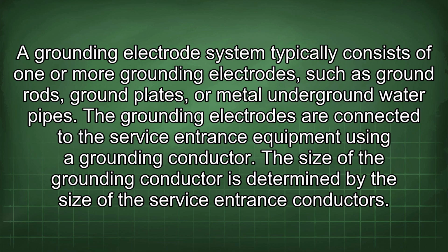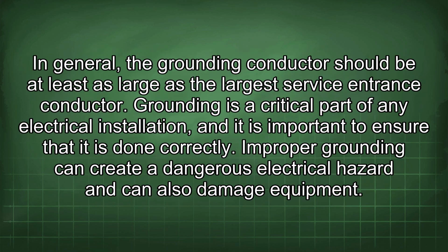A grounding electrode system typically consists of one or more grounding electrodes, such as ground rods, ground plates, or metal underground water pipes. The grounding electrodes are connected to the service entrance equipment using a grounding conductor. The size of the grounding conductor is determined by the size of the service entrance conductors. In general, the grounding conductor should be at least as large as the largest service entrance conductor.